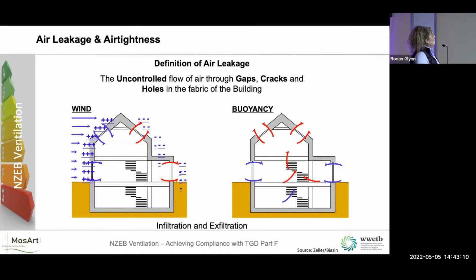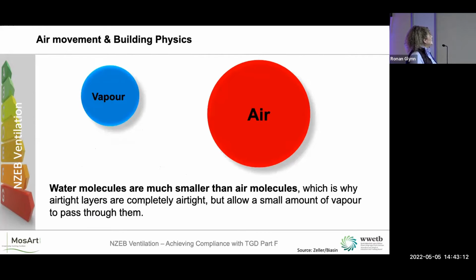Another thing we have to look at when we consider air permeability is the fact that condensation and vapor end up in the interstitial spaces in our building construction, especially in timber frame. So we have to understand that vapor molecules are much smaller than air molecules. So while you wrap something in insulation, you can stop heat loss or cold getting in, but the vapor will get through that batt insulation. That's why you have to have a vapor tight layer. It's really, really important.